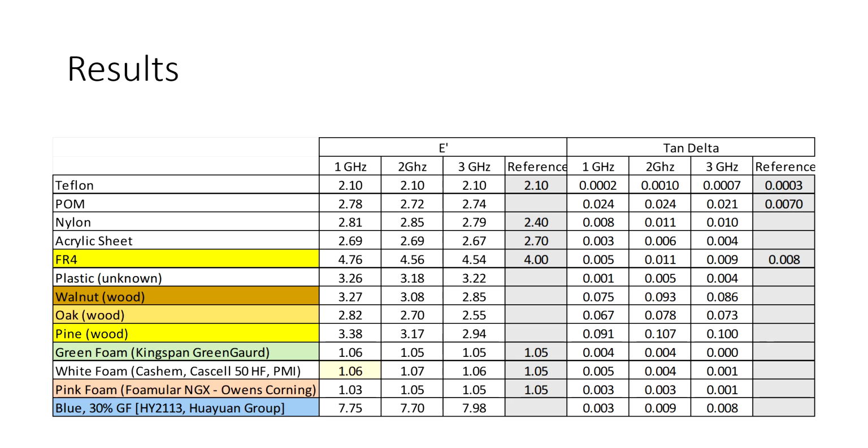All right, with all that done, we ran the calculations as shown in the previous equations, and these are the results. So the Teflon results you can essentially disregard, at least in terms of E prime, because these were used for calibration. Now note, I only used it to calibrate it at one frequency. I used the same constant for all frequencies, but again, this is empirical, so it's used to calculate. The rest of these results will give you an indication of how well the method is working.